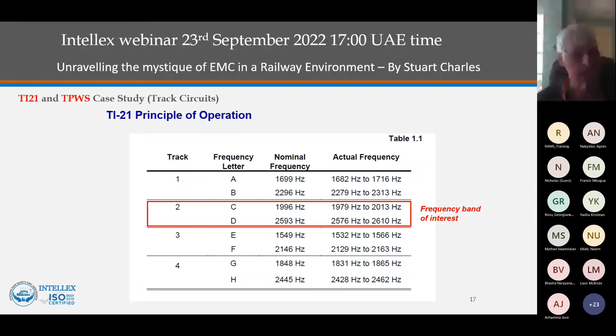Now, the concerns were that the 25th harmonic, so 2,593 times 25, because we've got a square wave with all these frequencies, or the 31st harmonic of 1996, could cause enough rail current to falsely trigger TPWS, the Train Protection Warning System, and be recognised as an in-band signal. EMI could have caused an accident on the train, braking or whatever.